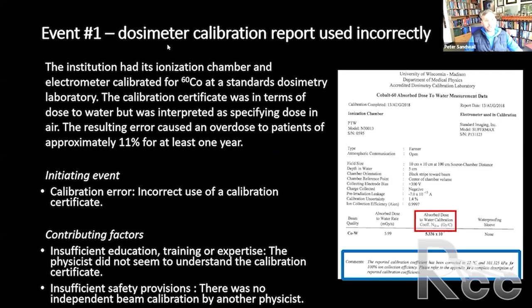So, dosimeter calibration report was used incorrectly. And this is actually a case where someone overthought it. And we are prone to do this as physicists. Many of us can overthink things. So the institution had its ionization chamber and electrometer calibrated for cobalt-60 at the Standards Dosimetry Laboratory. The calibration certificate was in terms of dose to water. You can see this absorbed dose to water calibration. This is the NDW, but was interpreted as specifying dose in air.